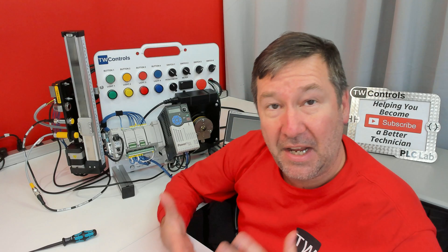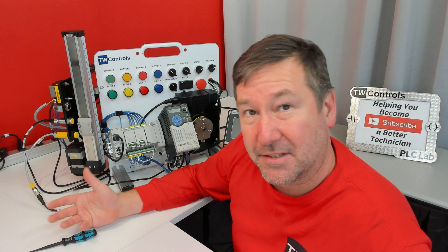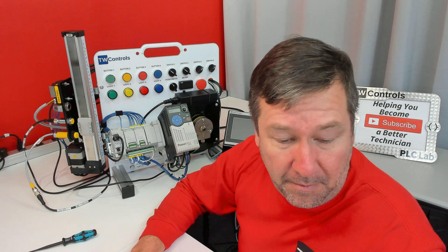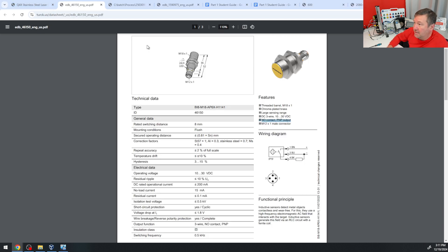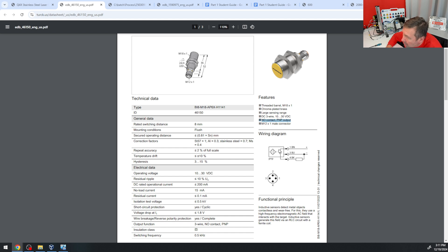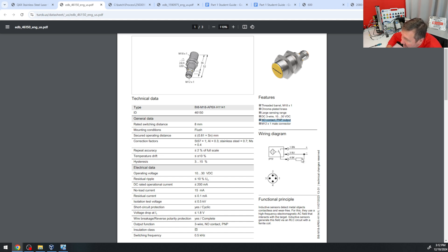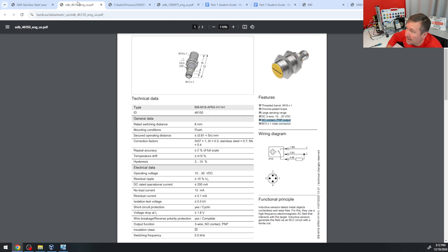So then we've got to figure out, we've got four wires coming out of these sensors. We've got to learn a little about it from the IO-Link. But let's go back and just refresh here. If we go back and we're going to start with our inductive prox, it says that the brown is the plus 24, the blue is the minus 24, and that's pin 1 and pin 3. And then this is the part that we get a little confused over, because it's just a little square block here. Well, just imagine the square block is the PLC. And so we're going to take the black wire, which is pin 4, to an input on the PLC. And then this little short piece going to the minus, that is COM0 right there. So that is this wire right here in that wiring diagram.